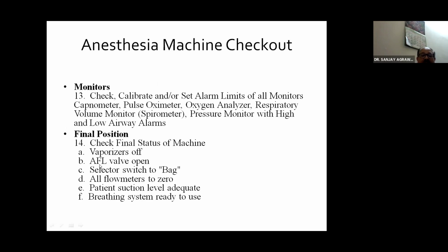Final check. Status of the machine: the vaporizer off, the APL valve open, select the switch to bag, all flow meters should be zero, patient suction level should be adequate, and the breathing system should be ready to use.